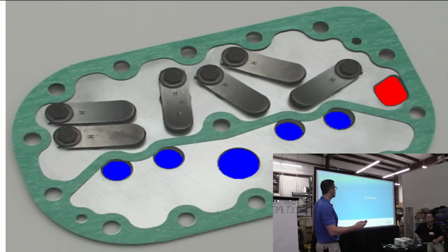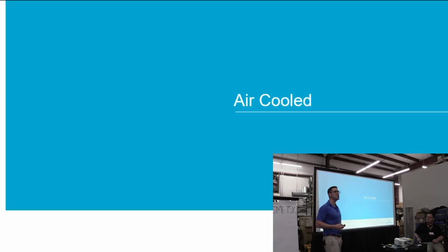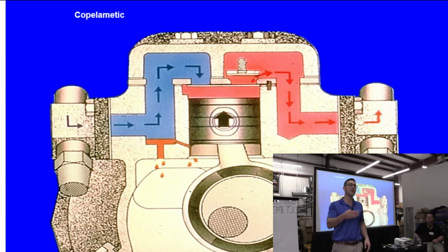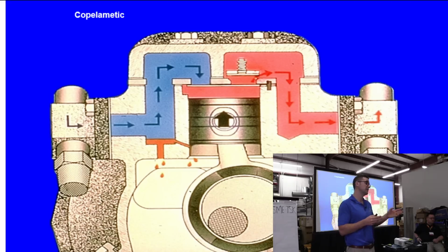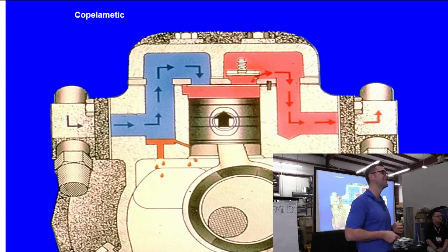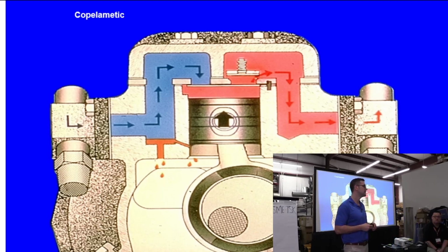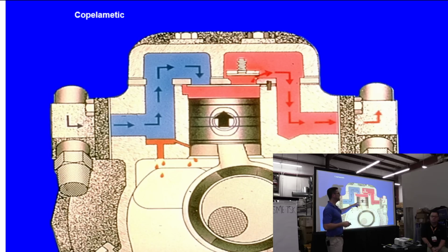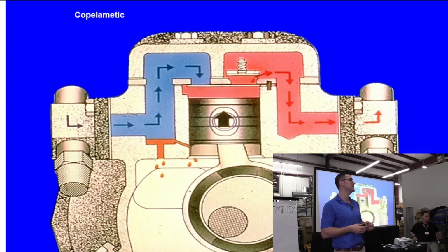Okay. Air-cooled compressor. What's one thing you can do when just looking at the Copeland compressor, if it's an air-cooled, K-body, to tell it's air-cooled? What's the first thing you're going to notice? Could have a fan on it, but that doesn't necessarily mean it's an air-cooled compressor. Nope. It's actually where the suction and discharge ports are. So if you see them right on the head, you could say that's an air-cooled compressor. Just a quick way to look at it.